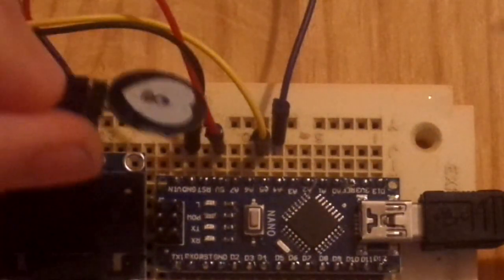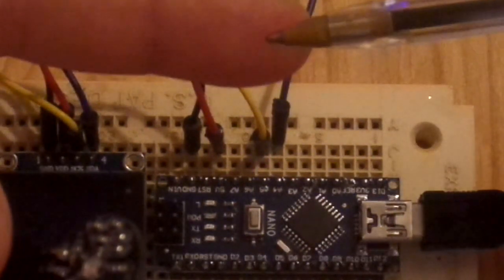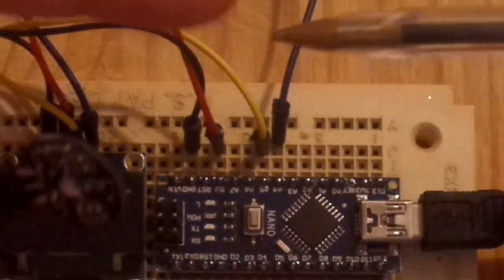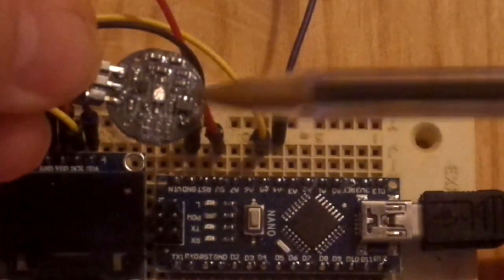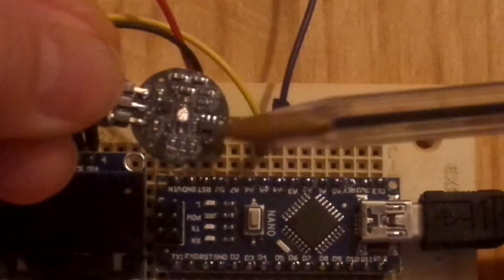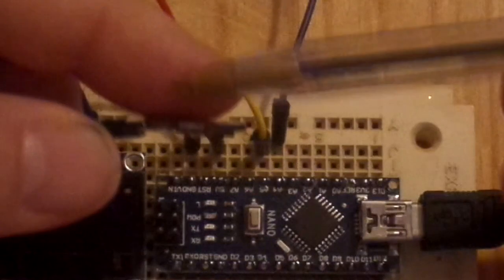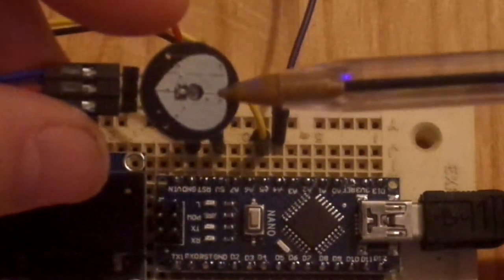Now, every time your heart beats, every time it pumps, it gives an extra push of blood. That extra push of blood ever so slightly expands your capillaries in your finger. They actually reflect slightly more infrared. Now, it is minute, but they've got a comparator on here, which will magnify the differences in infrared. So when the heart's not pumping, there'll be a certain amount of reflecting infrared. And when it does pump, then there'll be an extra bit of a surge of infrared reflected. That picks it up, amplifies it and sends that difference down a signal wire there.